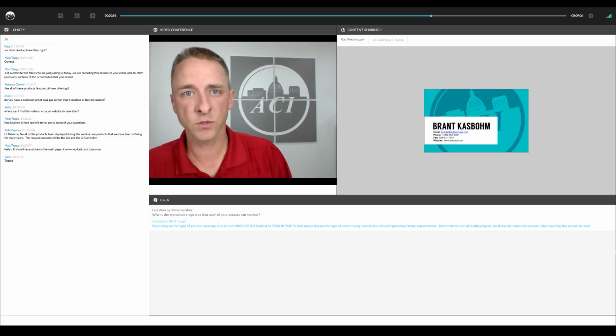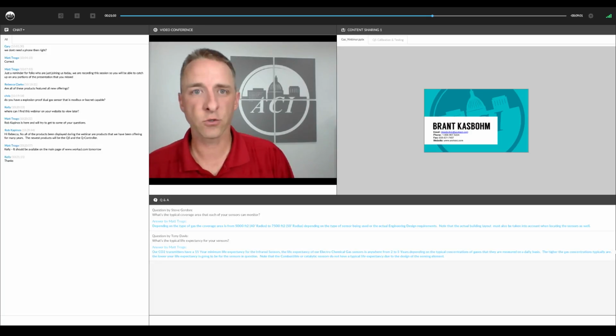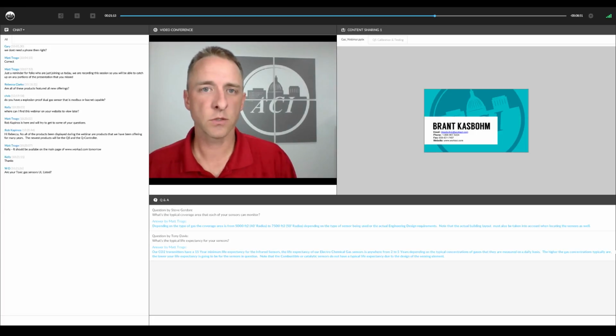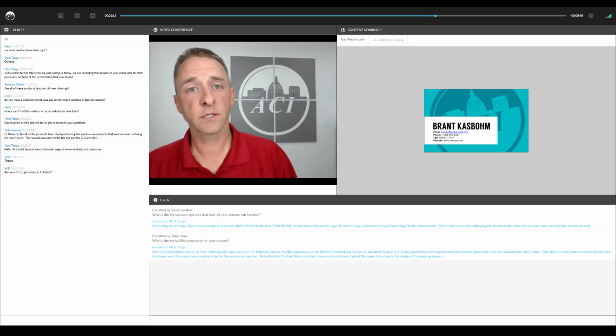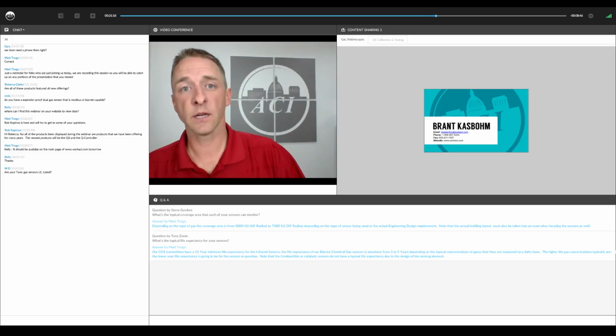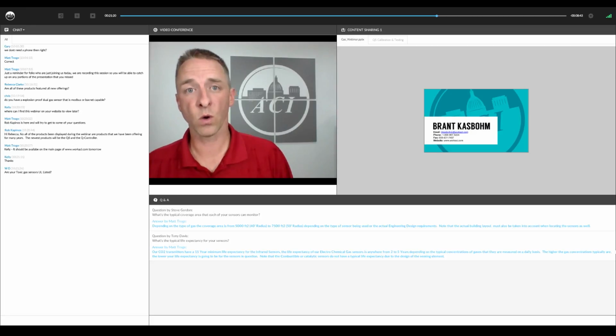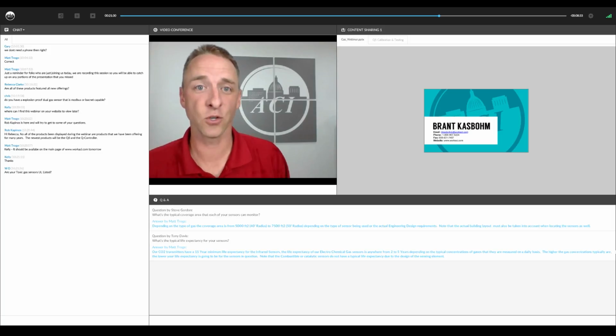But if you've got a job that requires hydrogen or ammonia or methane, some of the less common gases, we would typically build those to order, and so that might be an additional lead time. Typically, it's not more than a couple of weeks. And the reason we do that is, like I said, because these sensors have a shelf life. So we want you to have this sensor be in the field for 4 to 6 years and not have that life expectancy be taken up by sitting on our shelf or sitting on your shelf, and then the actual effective life expectancy might be 3 to 5 years instead of 4 to 6.